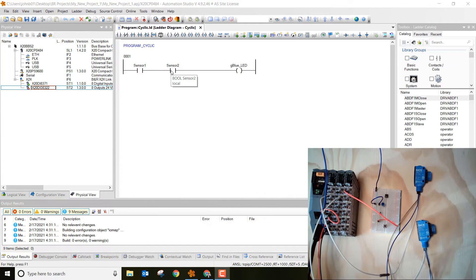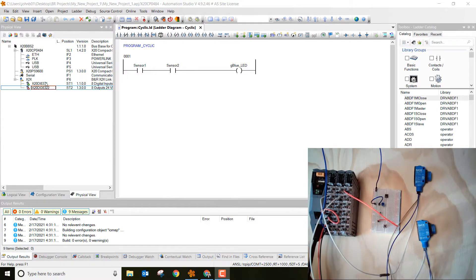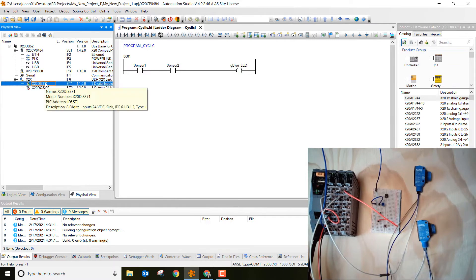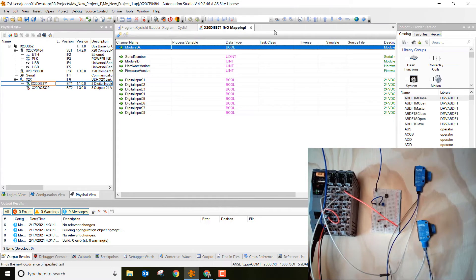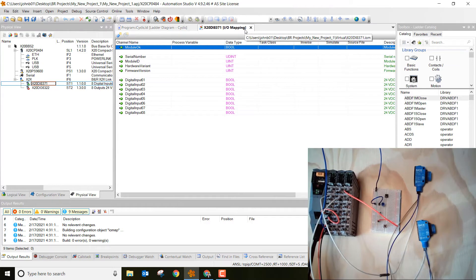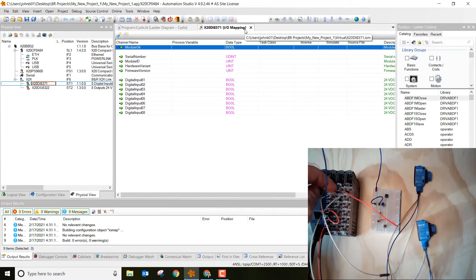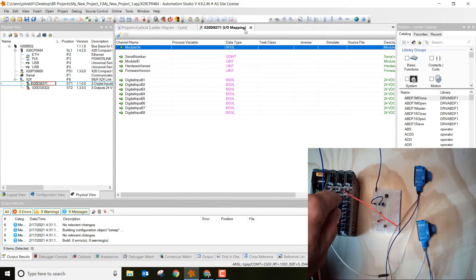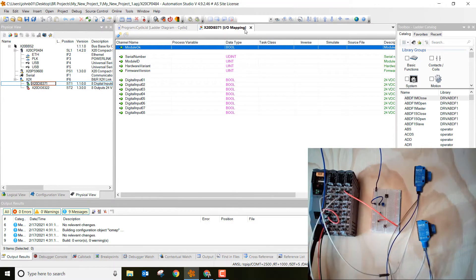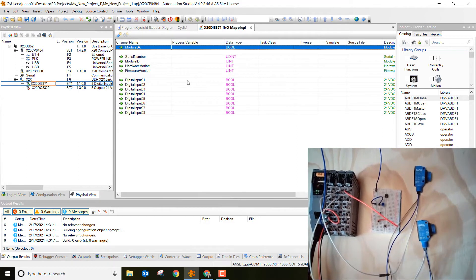So first what we want to do is we need to be in the physical view tab. This is the first part we need to do for mapping variables to specific outputs and inputs. Next, go to the digital input card, double click on it, and notice that it opens up IO mapping. You'll see over here that these two sensors each have a white wire. One wire is going to digital input 1 and one wire is going to digital input 4. So as you can see, we're going to want to map those variables to those digital inputs.